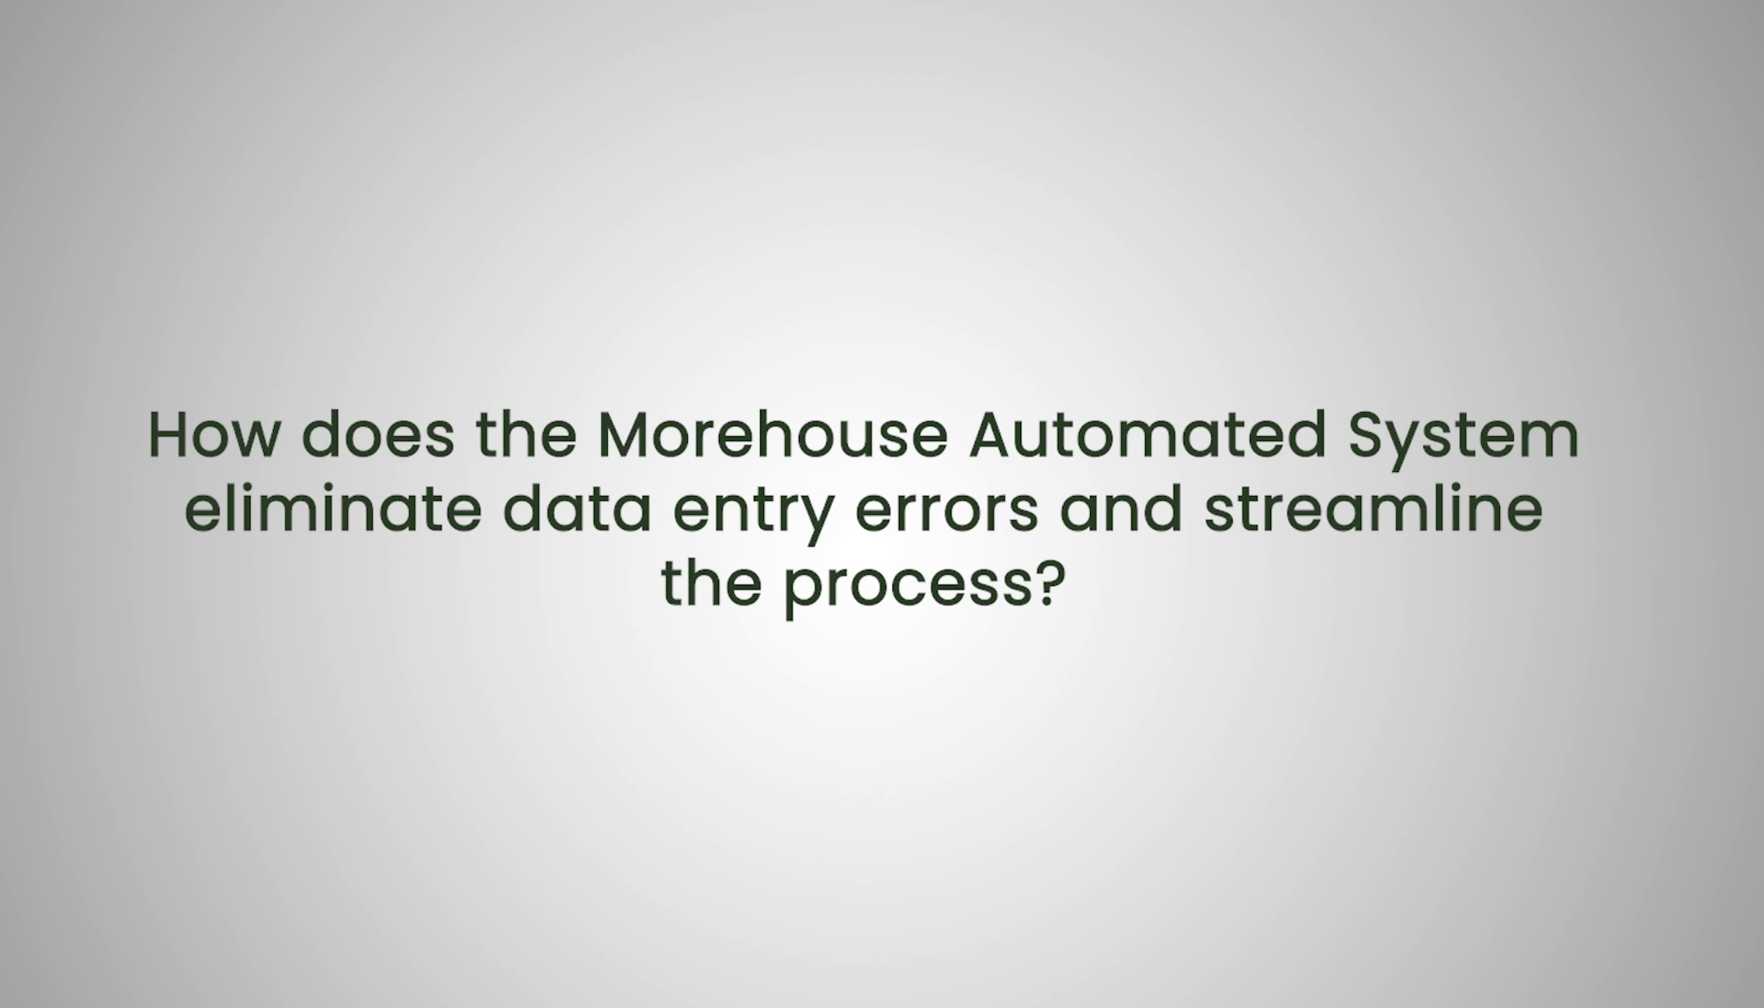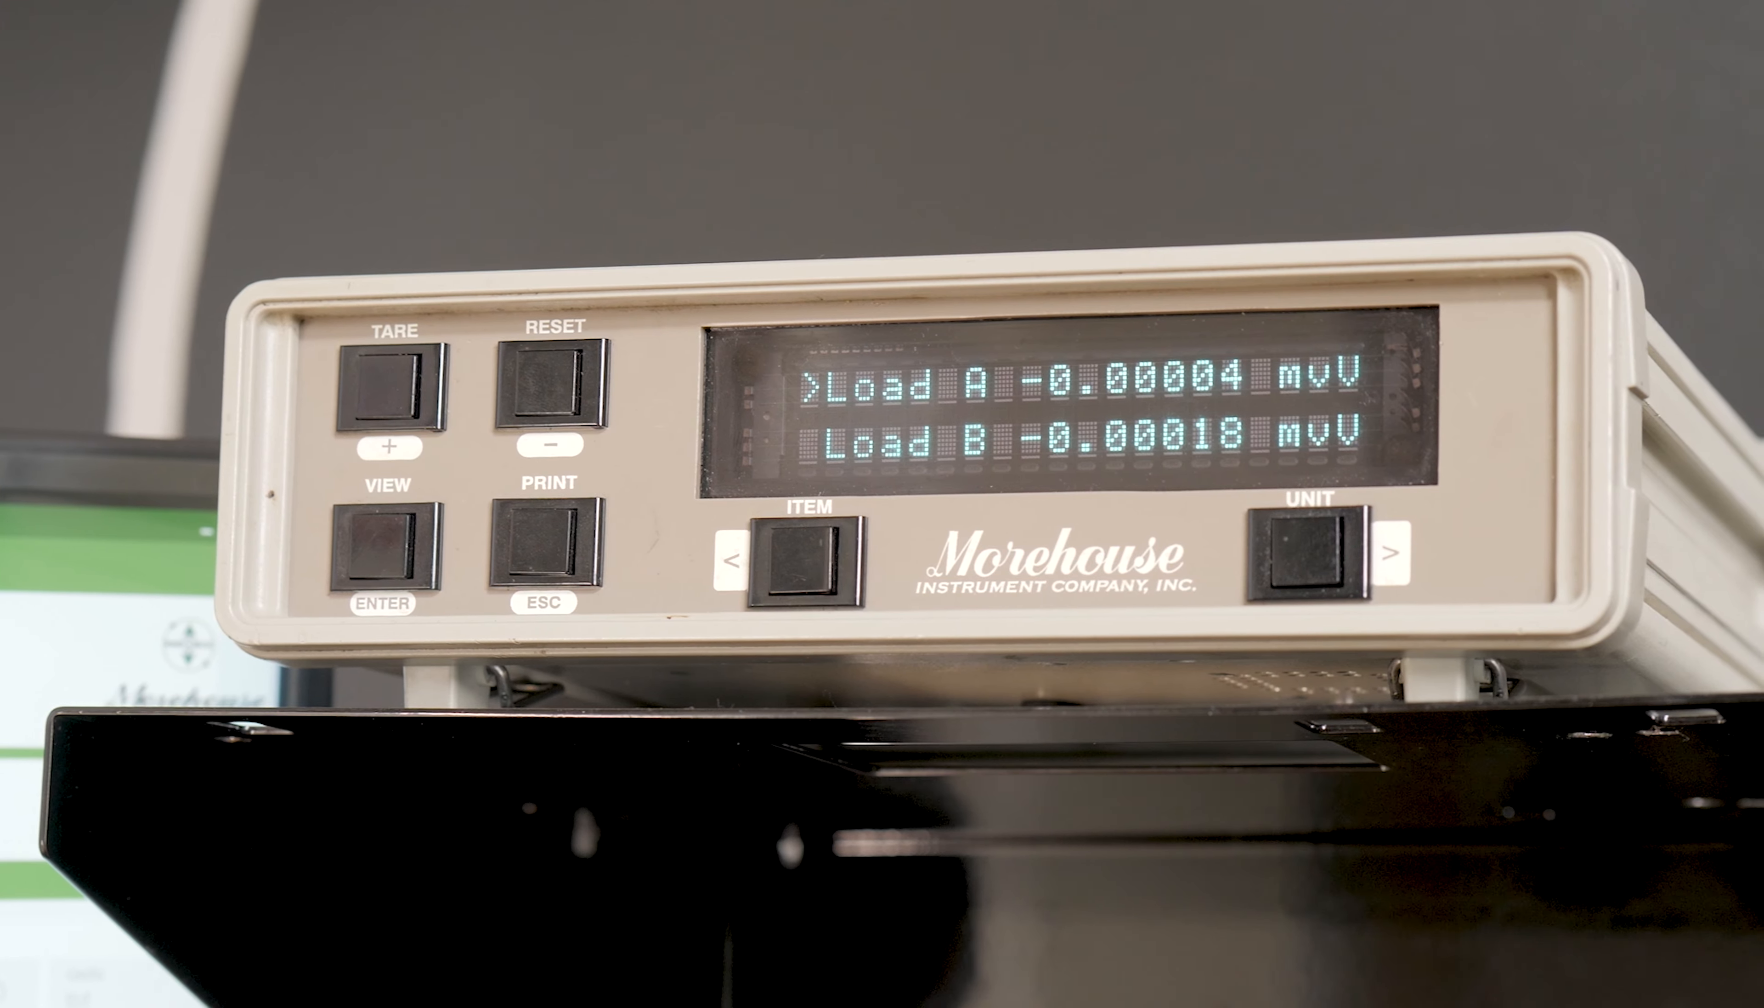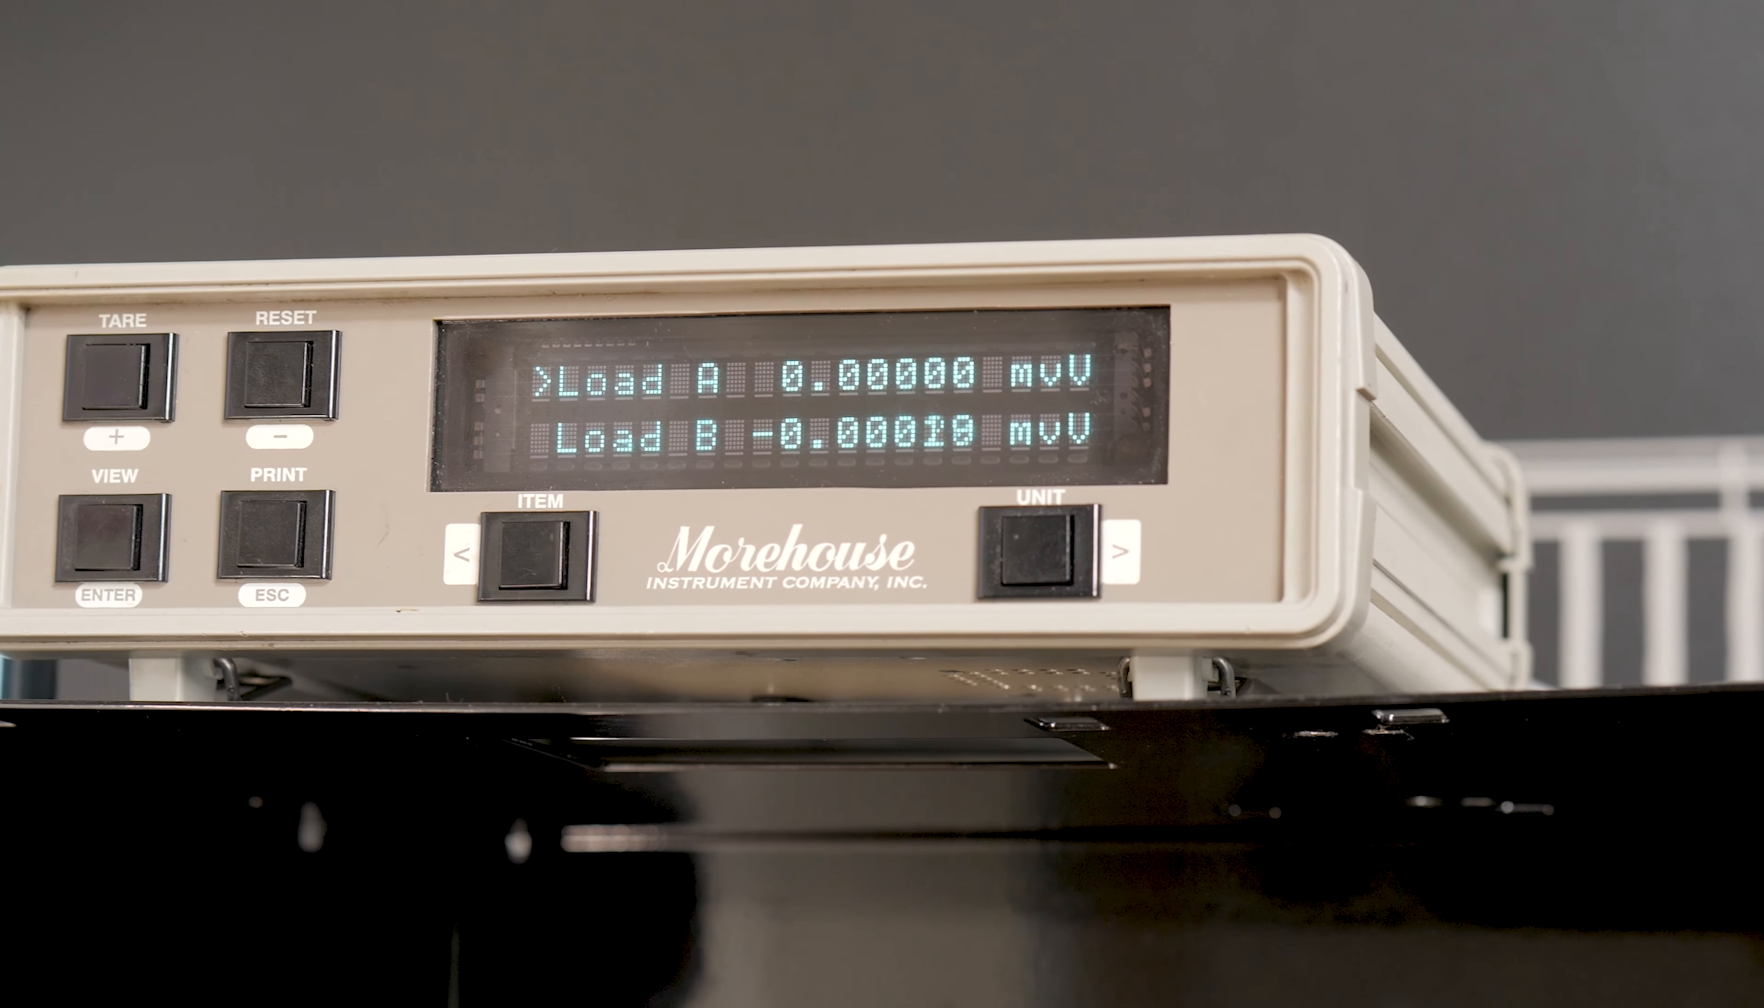How does the Morehouse automated machine eliminate data entry errors and streamline the process? If you're capturing readings from a Morehouse indicator, the system can get those readings automatically and within milliseconds of each other and average readings, which is all configurable in the software. You don't have to type anything in or write anything down. And so it eliminates all the typos. And then we're also continually adding new indicators to the library that this can read from. So if you need an indicator that's not a Morehouse indicator, we can talk about adding that.